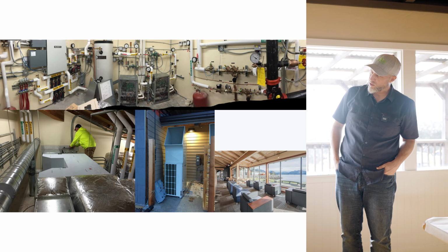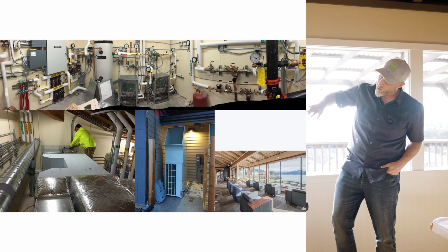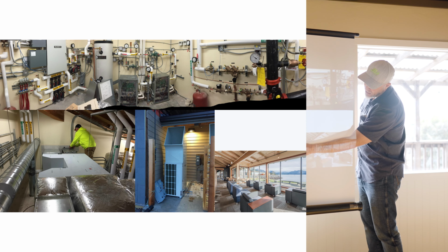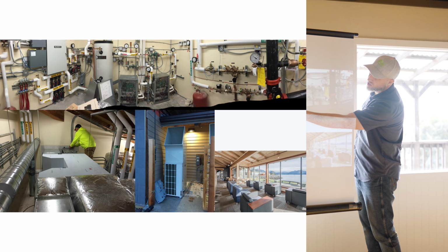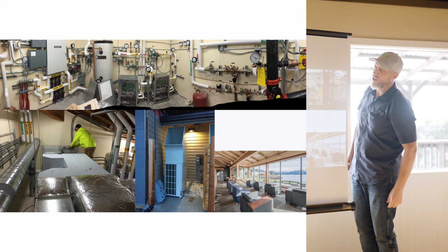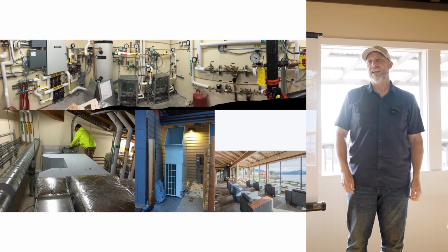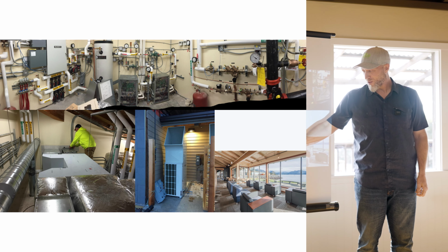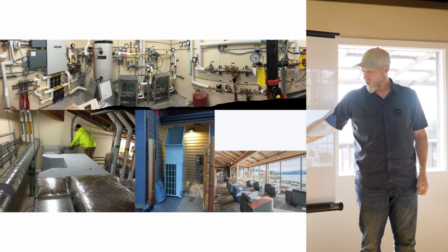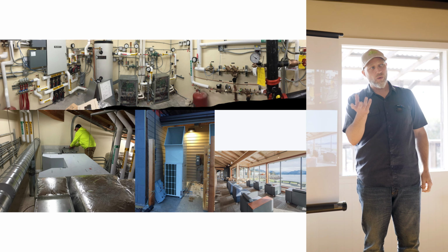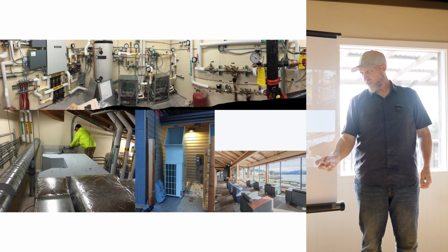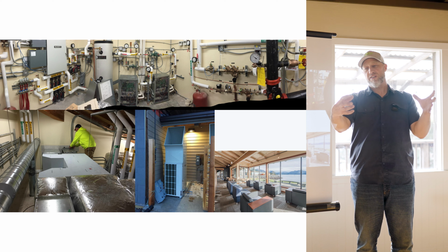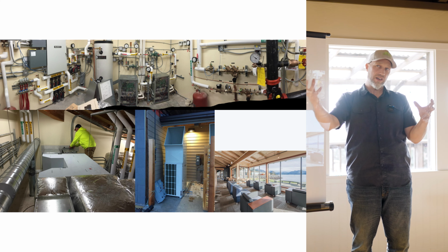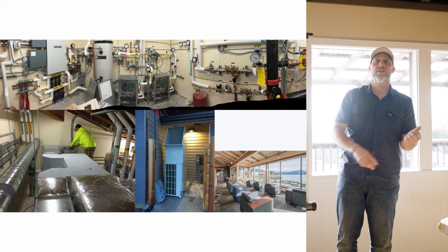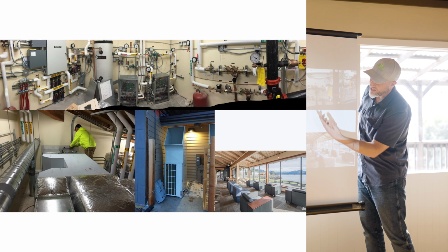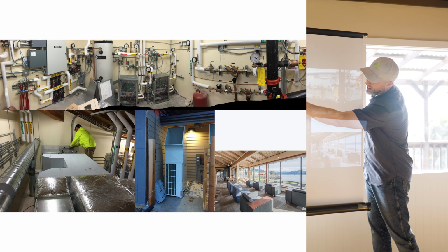I'm going to dig into the weeds a bit. Some photos of how it works: there's a VRF unit outside—variable refrigerant flow, variable refrigerant heat pump. This VRF transfers over to heat exchangers, and instead of routing the refrigerant all through the building, we converted to hot water and put it in the floor. We put the zones where the computer lab and the floor heat were together, so you can dump the heat from the computer lab into the floor. You can do that in most libraries. There's the radiant floor.